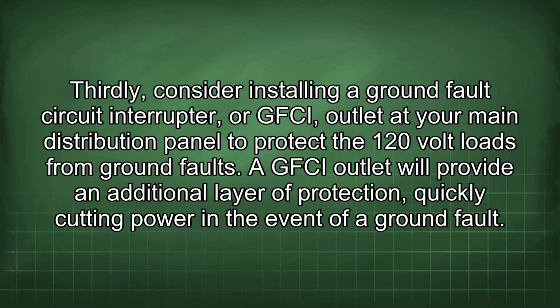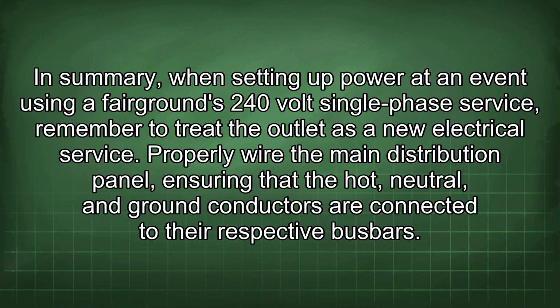A GFCI outlet will provide an additional layer of protection, quickly cutting power in the event of a ground fault. In summary, when setting up power at an event using a Fairground's 240-volt single-phase service, remember to treat the outlet as a new electrical service.